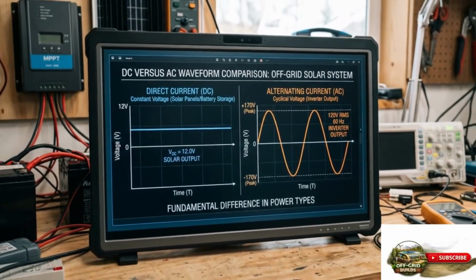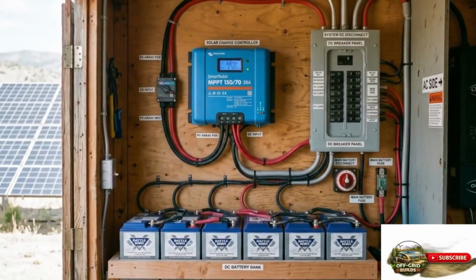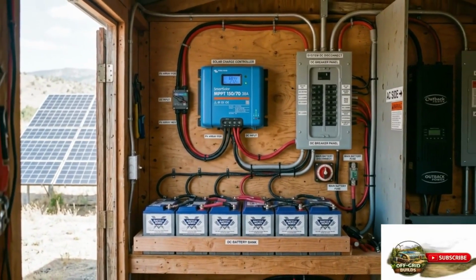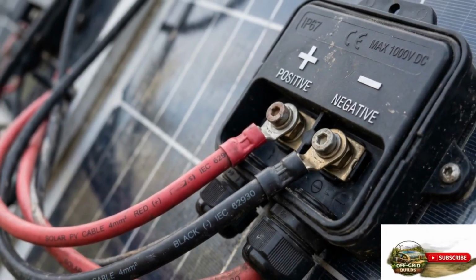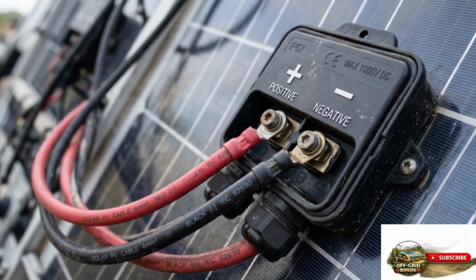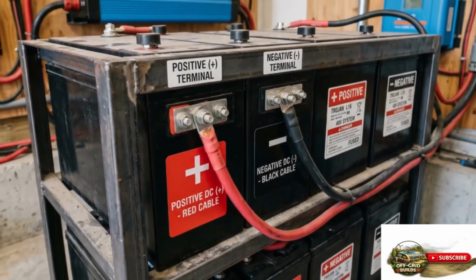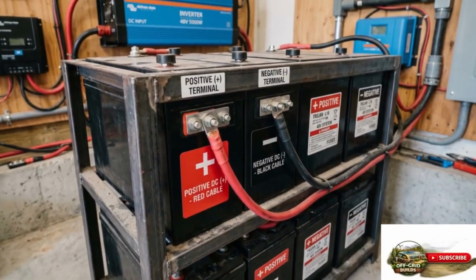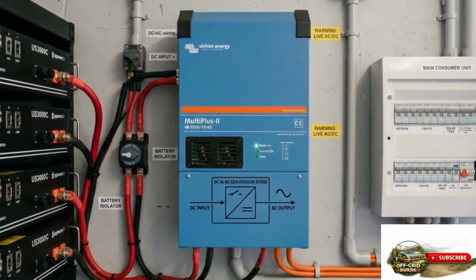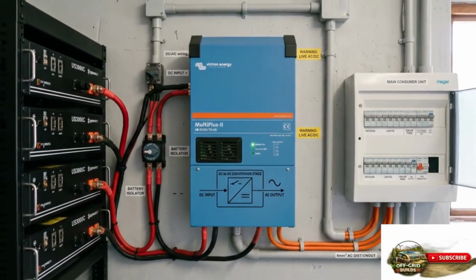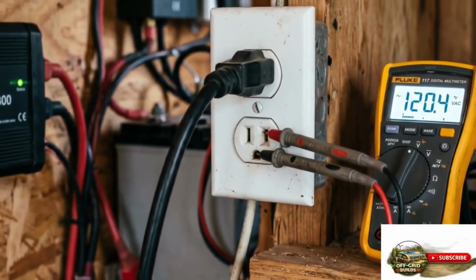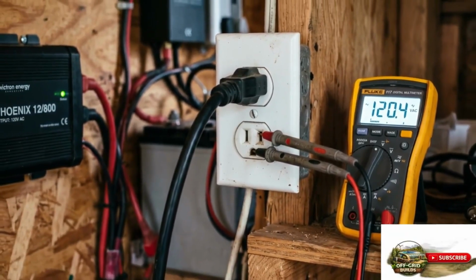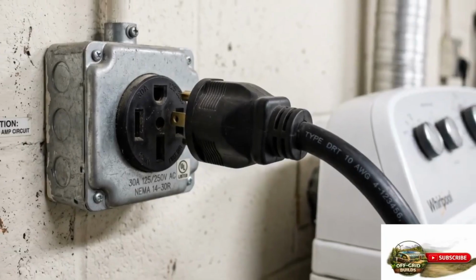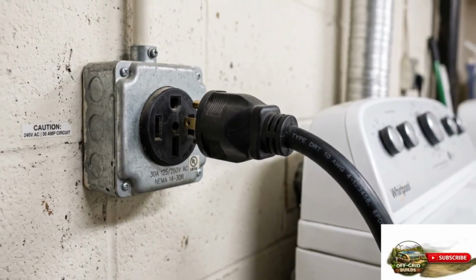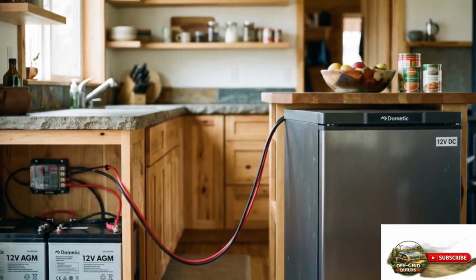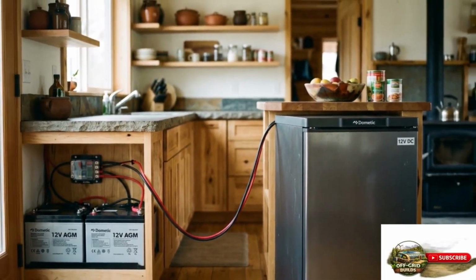Understanding DC versus AC in your system. An off-grid solar system manages 2 types of electrical current, and understanding the boundary between them is essential for understanding how the system components connect and interact. Solar panels produce direct current, which is electricity that flows in one direction only from the negative terminal to the positive terminal continuously. Batteries also store and release direct current. The charge controller, which manages the power flow from panels to batteries, operates entirely in direct current. This DC portion of the system operates at voltages that depend on the system architecture, typically 48 volts for larger residential off-grid systems.